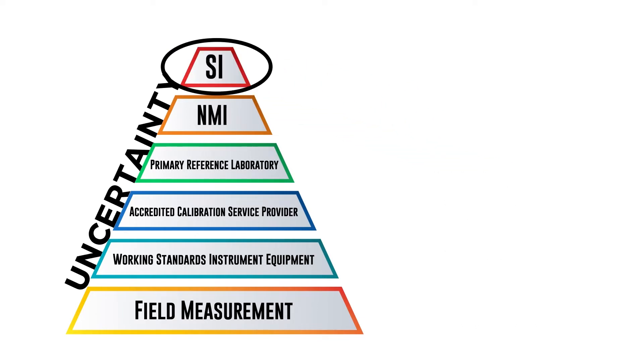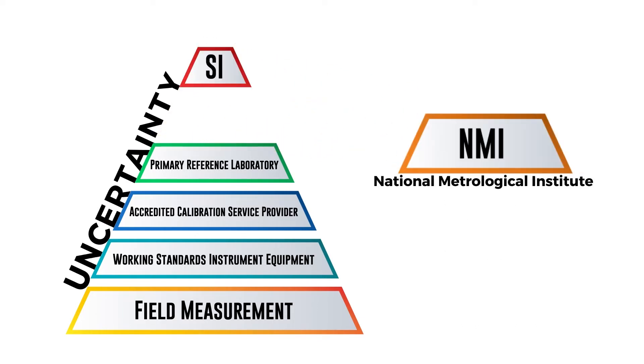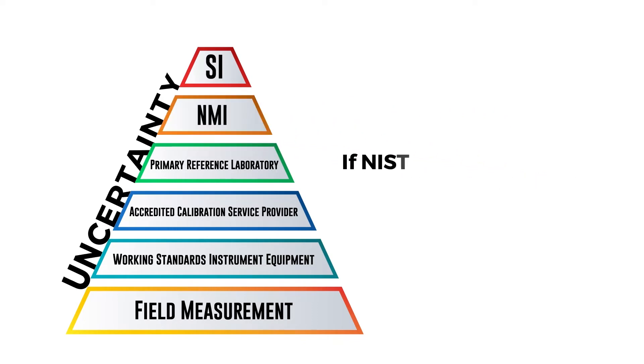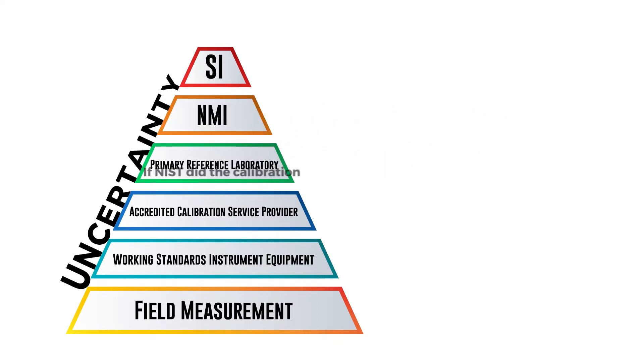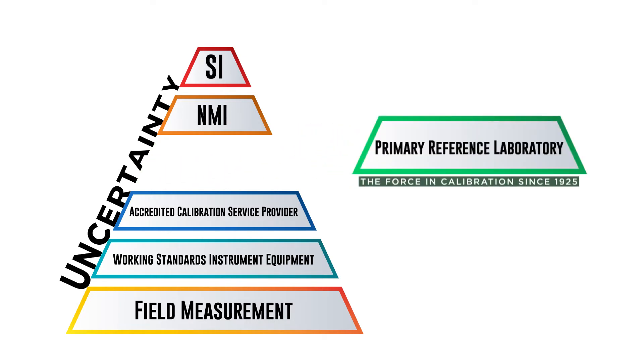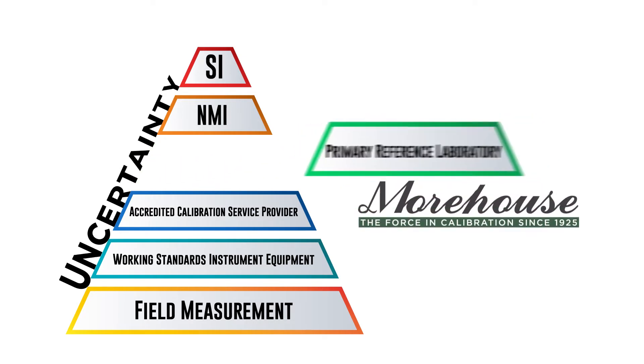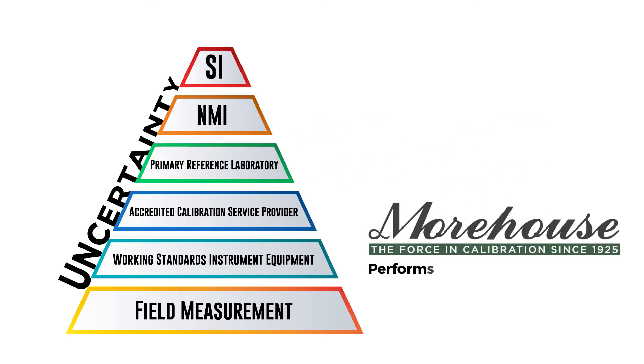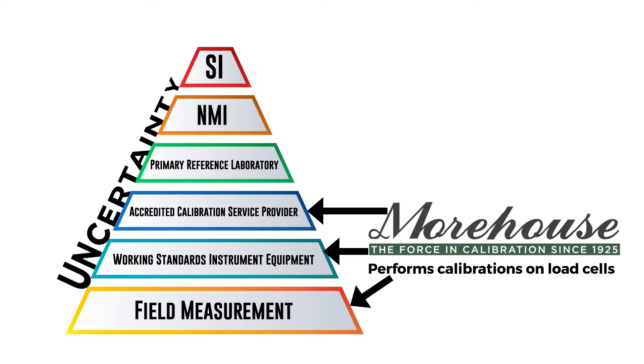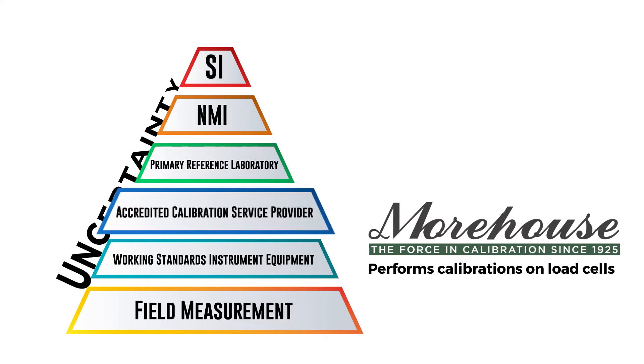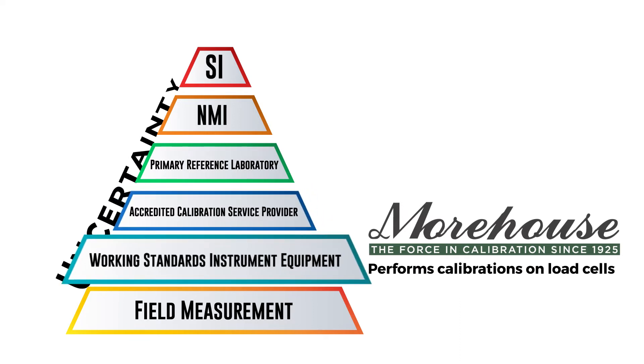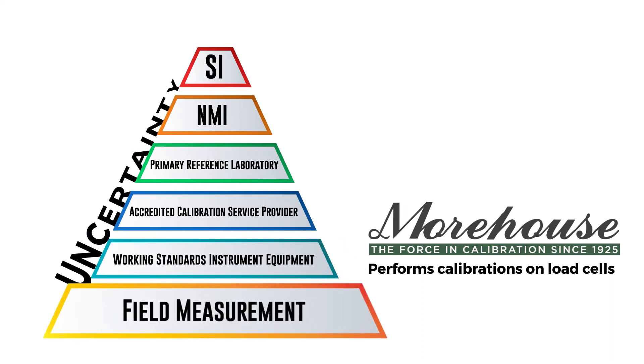The pyramid starts with SI at the top, then NMI, National Metrological Institute, like NIST. If NIST did the calibration of the force weights, then the next tier would be a primary reference laboratory like Morehouse. Morehouse performs calibrations on load cells for the lower tiers — accredited calibration suppliers, followed by working standards, who in turn calibrate field equipment.